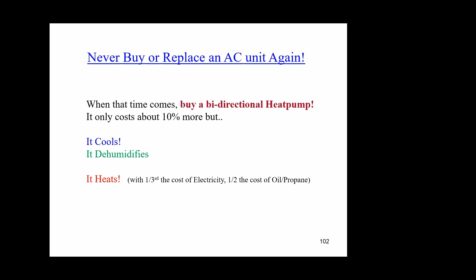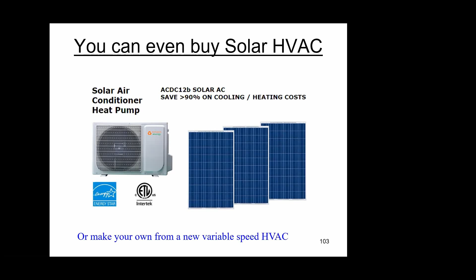In fact, these mini split heat pumps now all use variable speed motors. To get a variable speed motor, the first thing they do is full wave rectify the incoming AC line to DC, then use a variable speed DC to DC converter to control the speed. Because you're starting off with high voltage DC, you can put together however many solar panels you want and tap right into that DC point, running the HVAC heat pump air conditioner unit on solar directly.